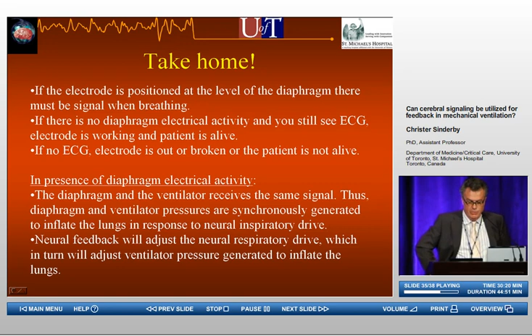In the presence of diaphragm electrical activity, though, the ventilator and the diaphragm receive the same signal, and thus the diaphragm and ventilator pressures are synchronously generated to inflate the lungs in response to neural inspiratory drive, and this is important. And the neural feedback will adjust the neural respiratory drive, both within the breath and between breaths, which in turn will adjust the ventilator pressure generated to inflate the lungs.